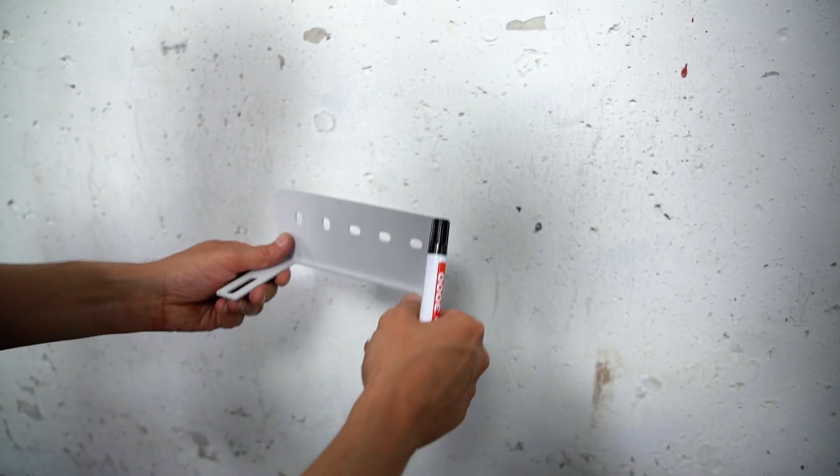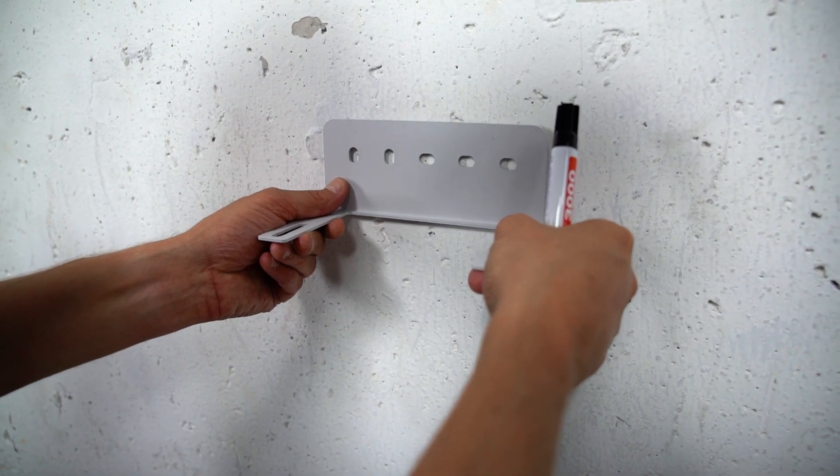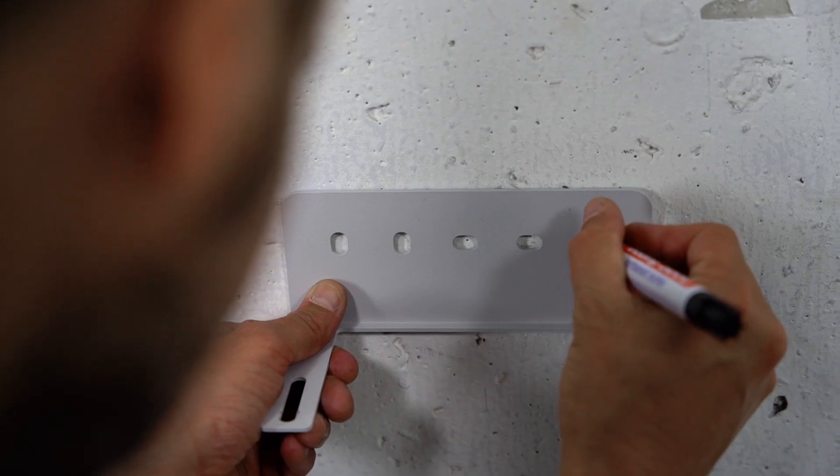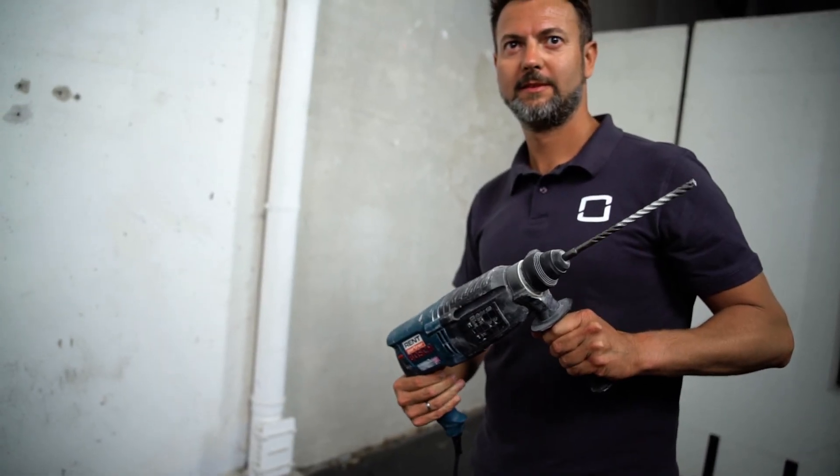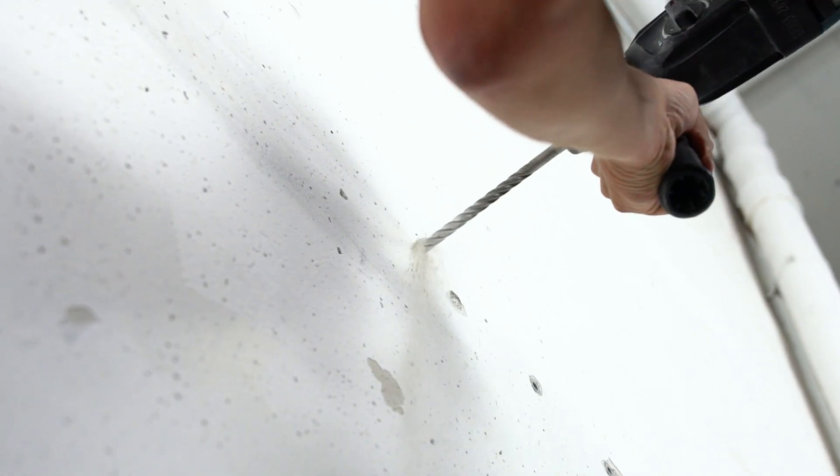The bracket will be mounted on the top battery module. After defining the right position, you need to mark the position of both outermost holes for drilling. Take your drill with the 10 mm drill bit and drill at least 70 mm deep into the wall at the marked points.